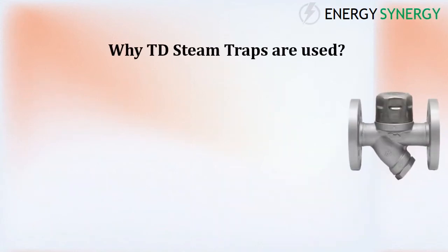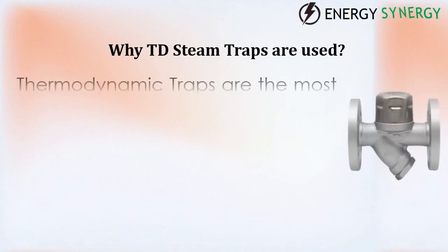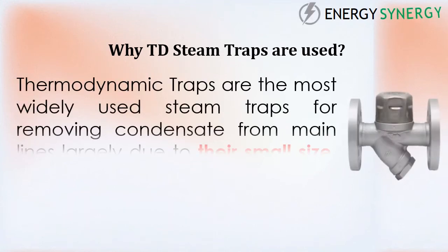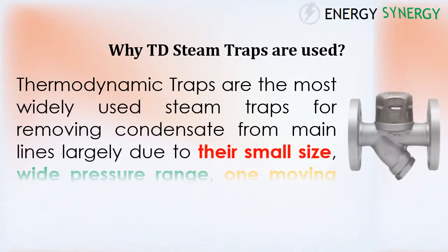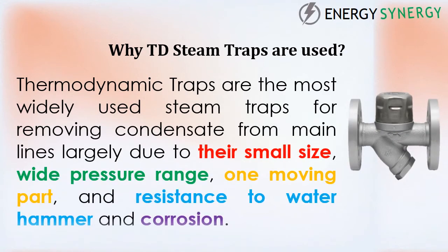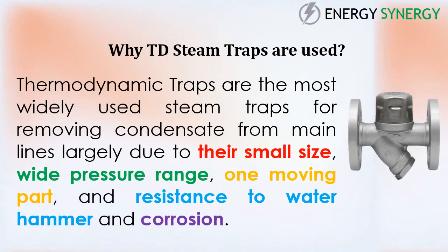Why use thermodynamic steam traps? Thermodynamic traps are the most widely used steam traps for removing condensate from main lines, largely due to their small size, wide pressure range, one moving part, and resistance to water hammer and corrosion.